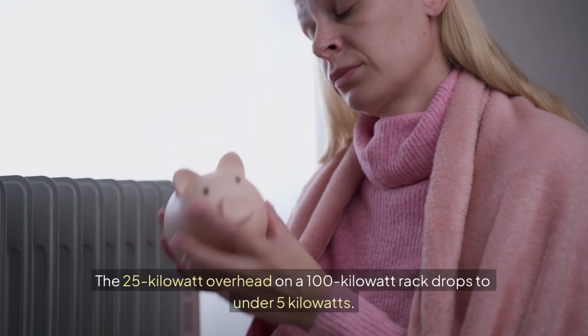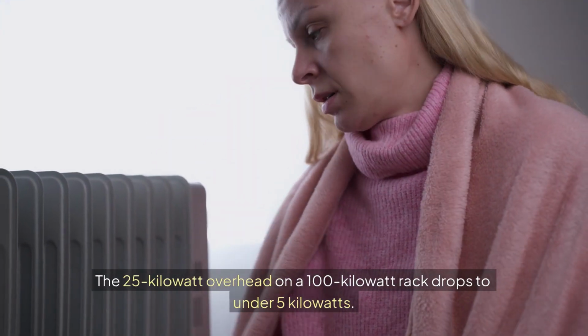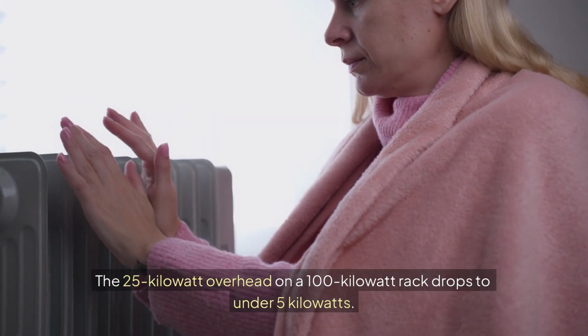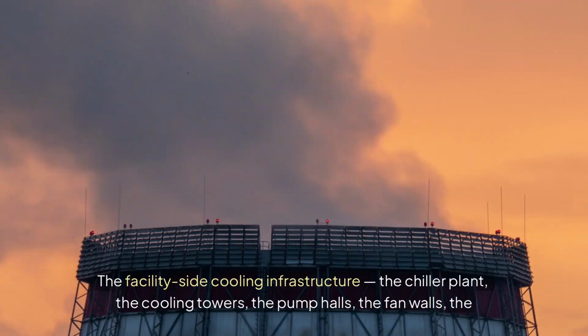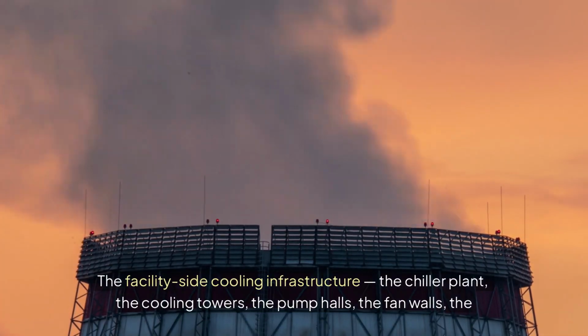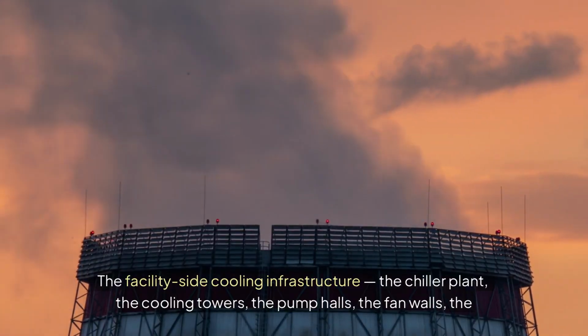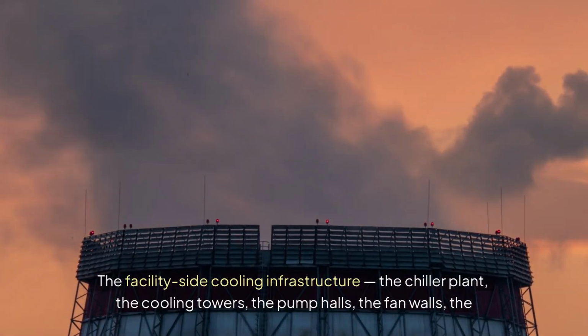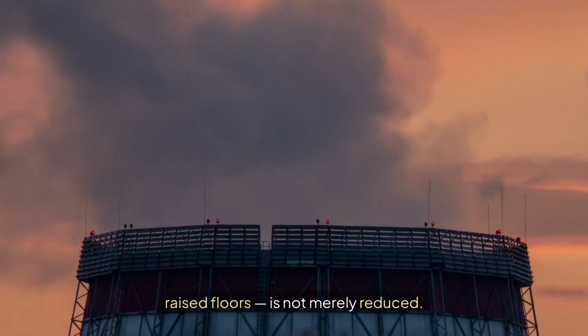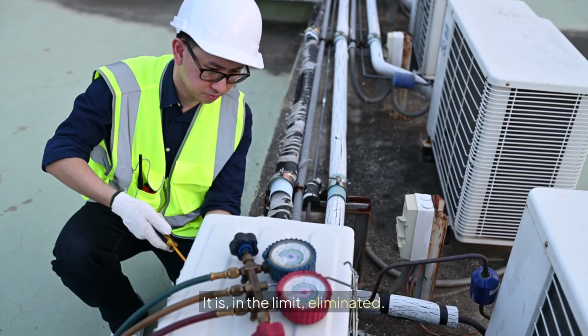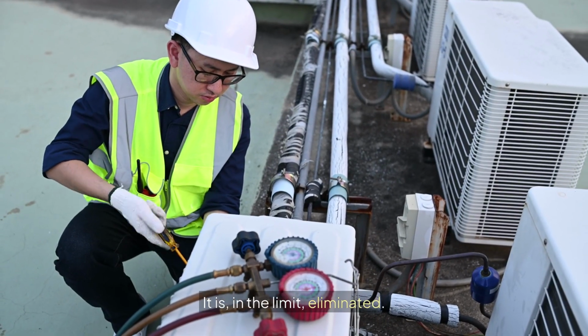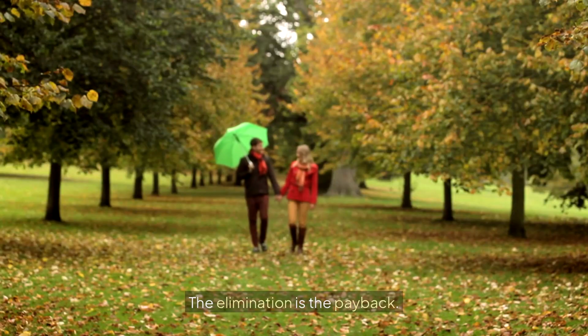The 25 kilowatt overhead on a 100 kilowatt rack drops to under 5 kilowatts. The facility-side cooling infrastructure, the chiller plant, the cooling towers, the pump halls, the fan walls, the raised floors, is not merely reduced. It is, in the limit, eliminated. The elimination is the payback.